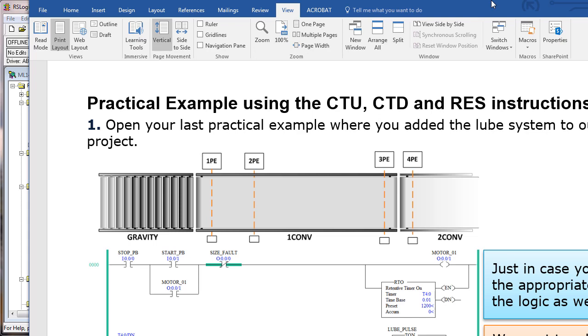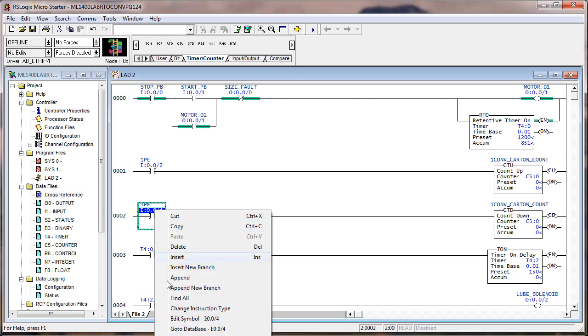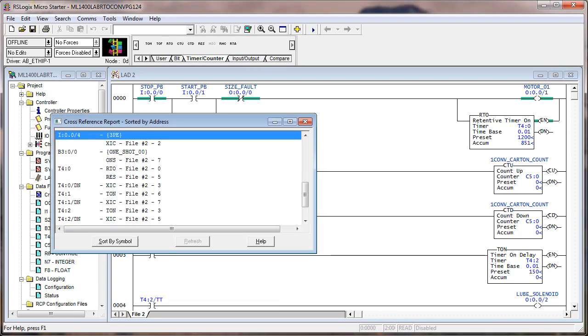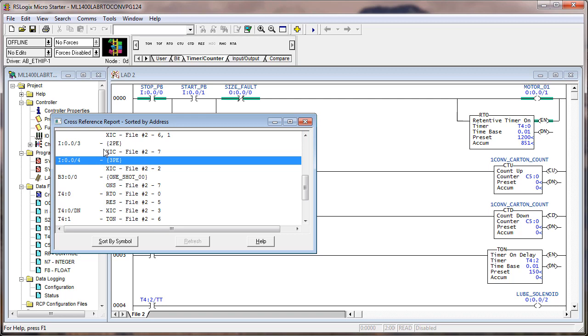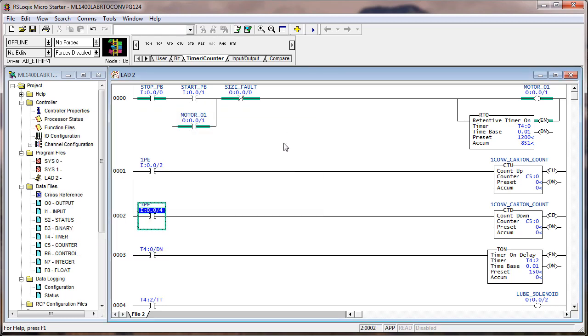I had you add two new rungs and put them right below the conveyor rung. This is the conveyor, conveyor one. When you put in the pointer input colon zero dot zero slash four, it may have popped up with something else for text. And that's fine. A way to make sure that you're not already using that input is to right-click on it and go to cross-reference. And you see there's only one use of it. See, this is input. And I can scroll up a little bit to make sure that there's not something missing up above. But input four, which now I've labeled 3 PE, is only used in file two rung two. And the next bit used in memory is B300. So if I click on that, it'll take me right to that usage from the cross-reference.